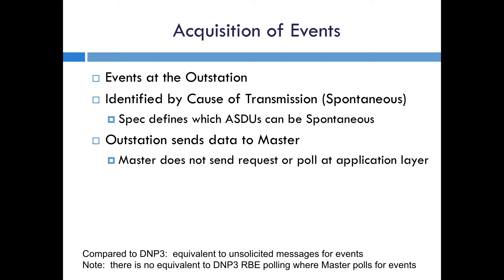Note that although spontaneous transmissions and DNP3 unsolicited responses are similar, there are a few differences. In particular, with DNP3 the master can suppress unsolicited responses — it can send a command telling the outstation to stop sending them. You cannot do that in IEC 60870-5. There is no disable for a spontaneous message. The outstation can choose to send them or not, but the master cannot tell the outstation to stop sending them.